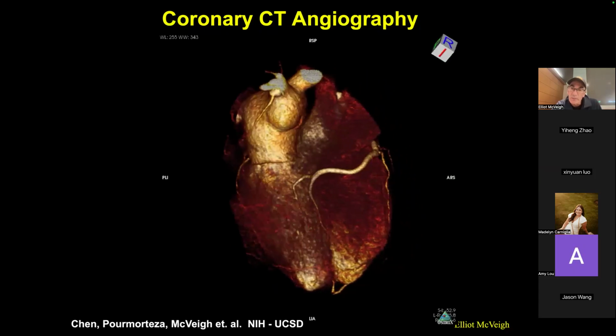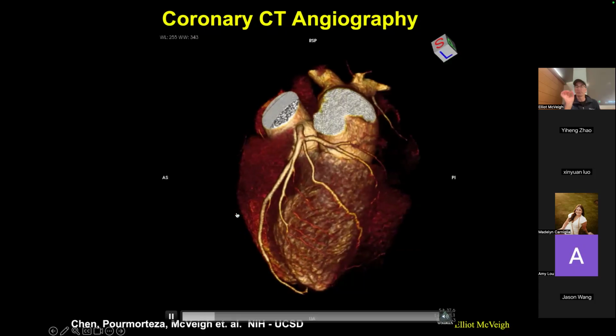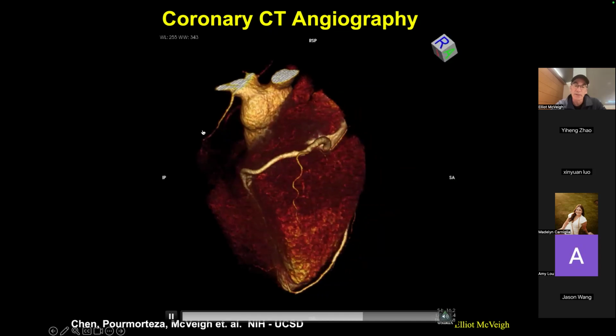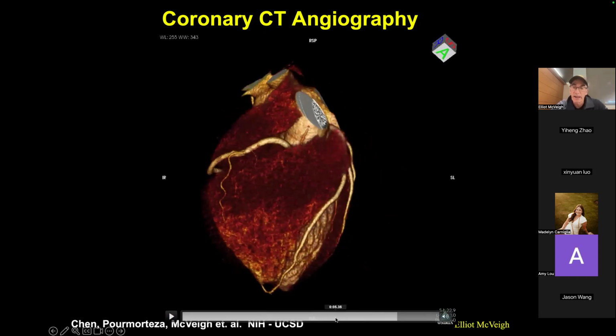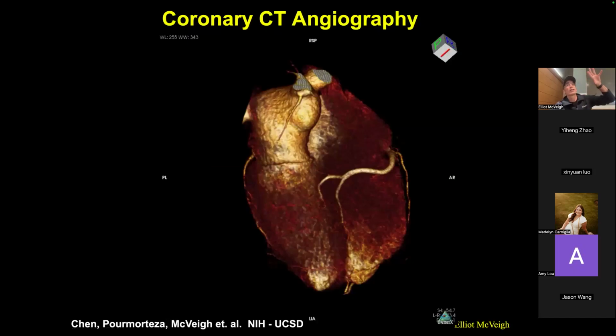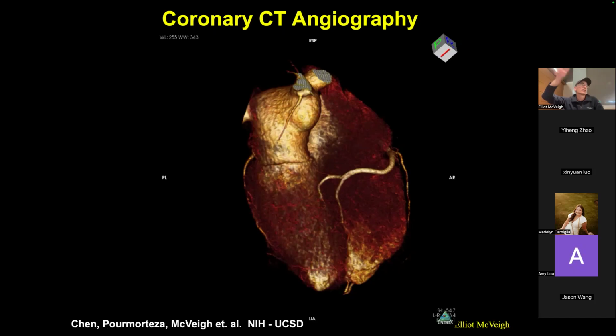And you can see a very small descending vessel here that's coming off the right coronary. It's pretty fine in its structure and it's all resolved. This vessel is not moving much at the time that we're taking this image, right? So it's really clear all the way down. If we took this image while the heart was in mid-contraction, mid-systole, this would be a big old blur up and down this way because it moves up and down when the heart contracts. It would not only be a blur, it would be like a cycloid pattern. It's a very interesting motion artifact pattern in CT.